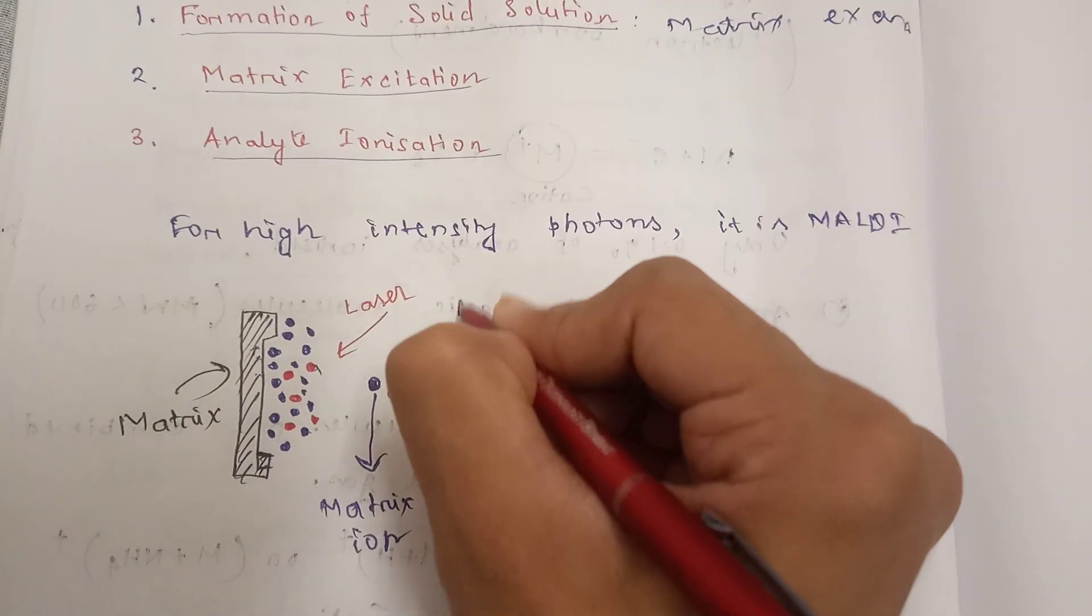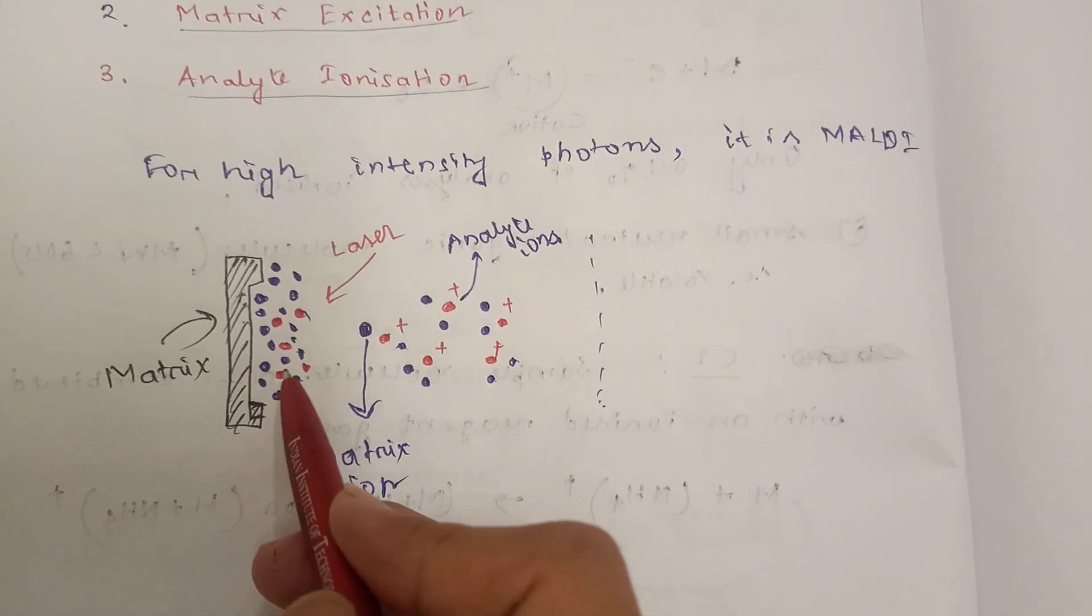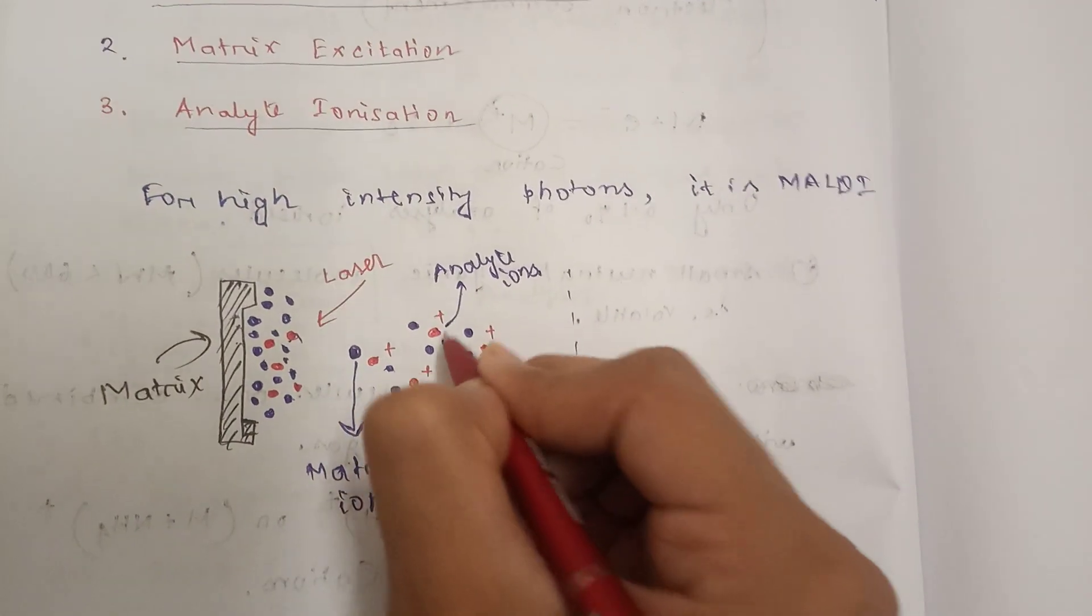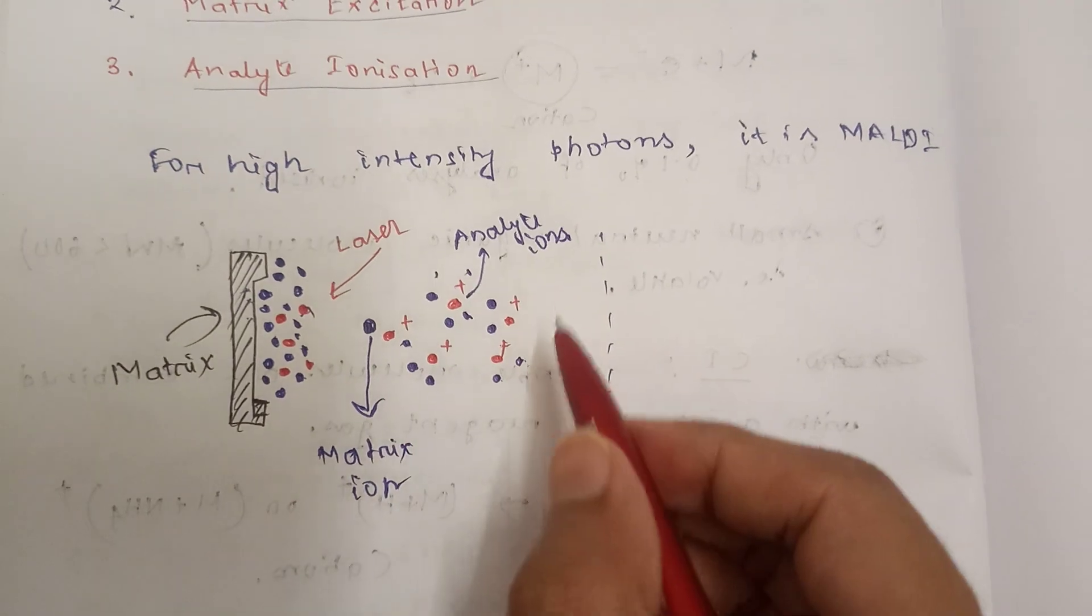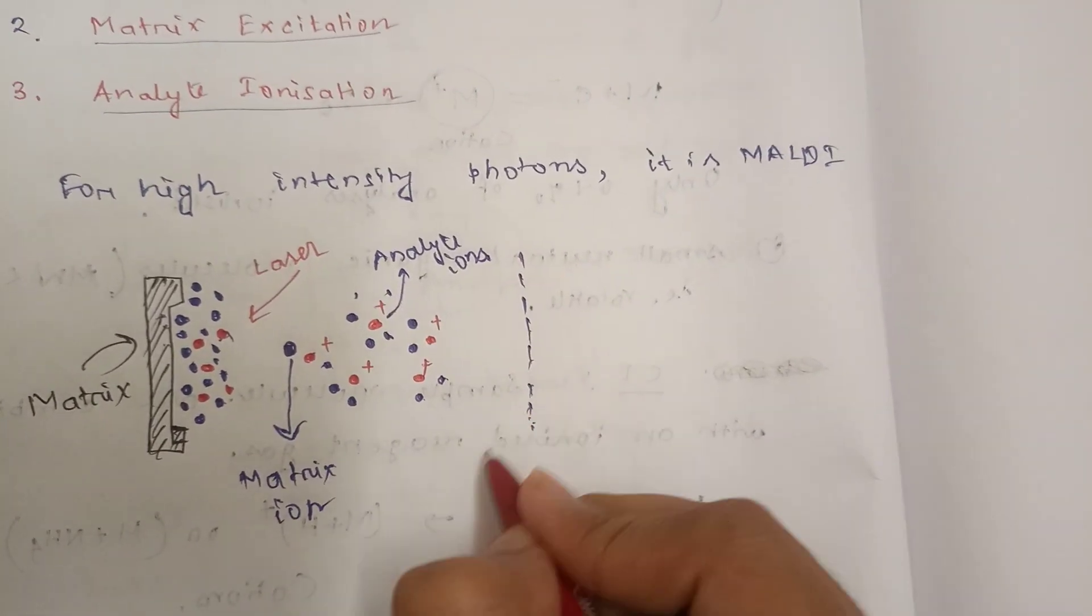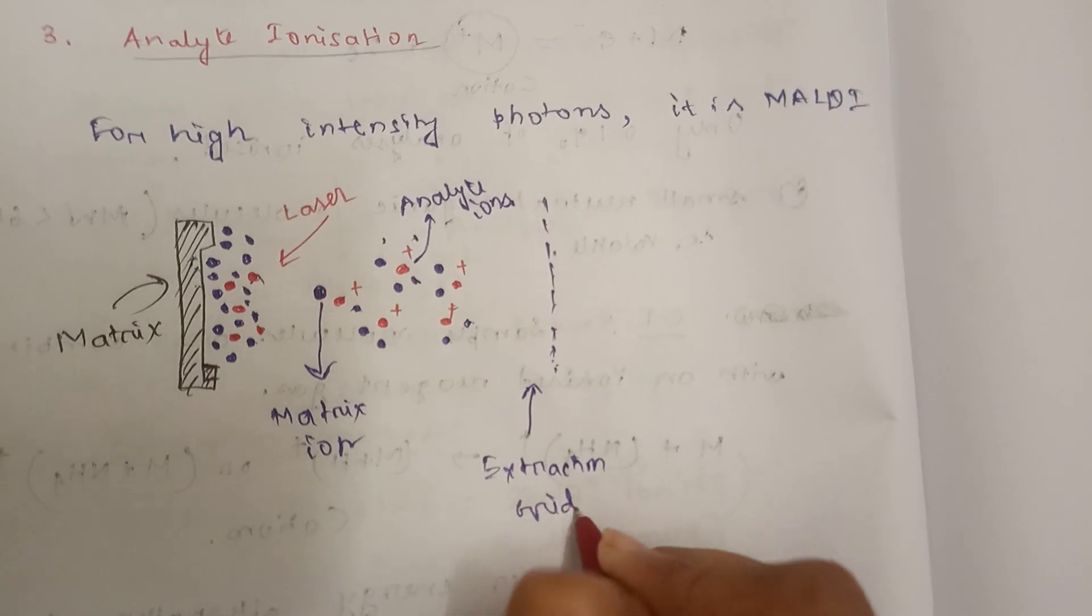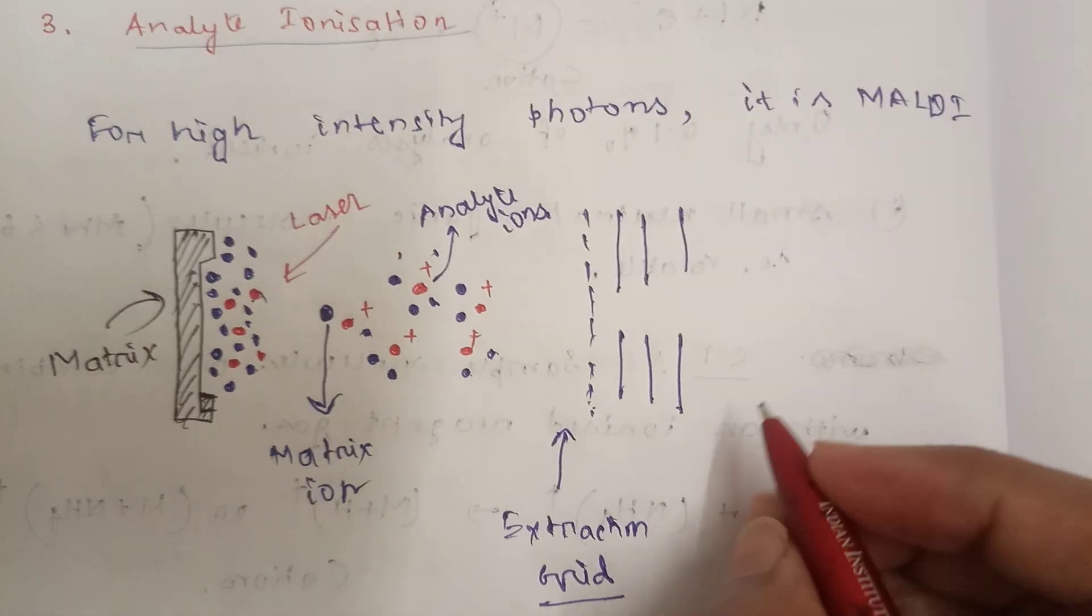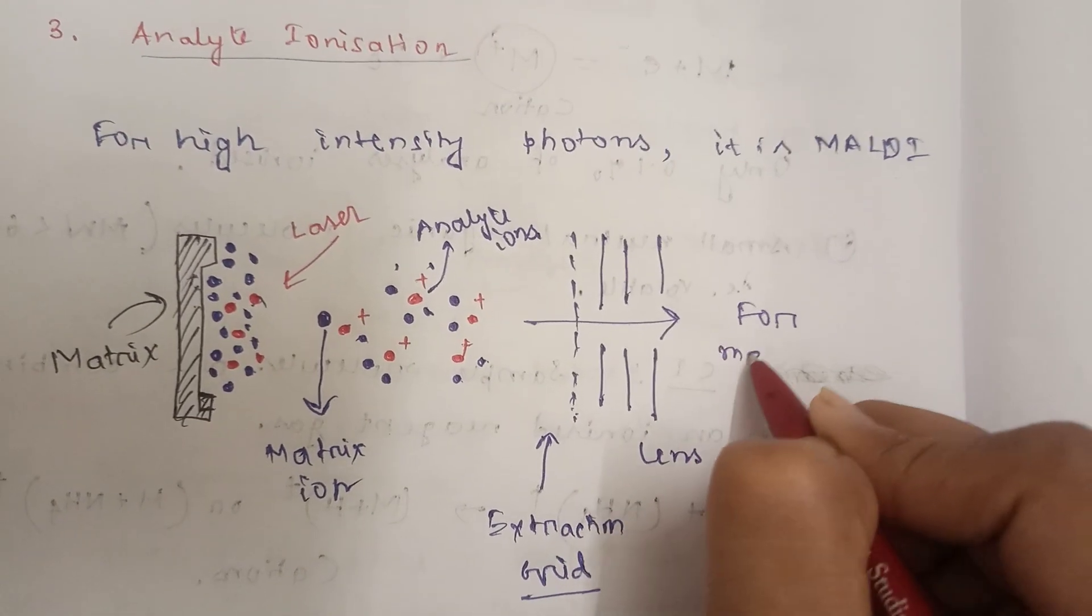These clusters ejected from the surface consist of analyte molecules surrounded by the matrix and salt ions. The matrix molecules evaporate away from the clusters to leave the free analyte in gas phase. Here you can see there is an extraction grid, then there will be some focusing lens, and then it will pass for mass spectrometer.